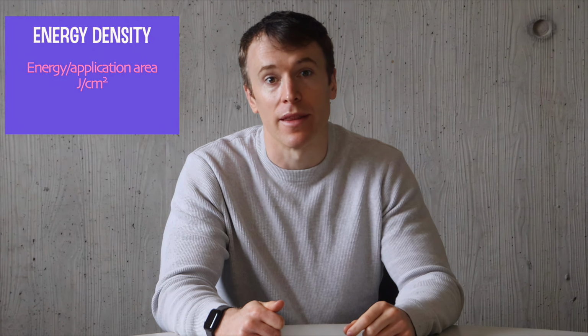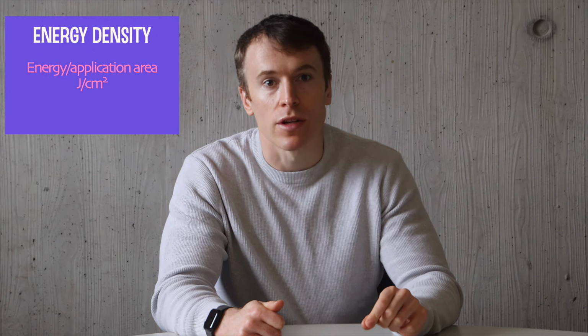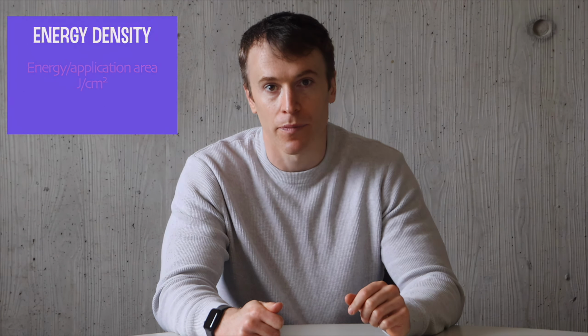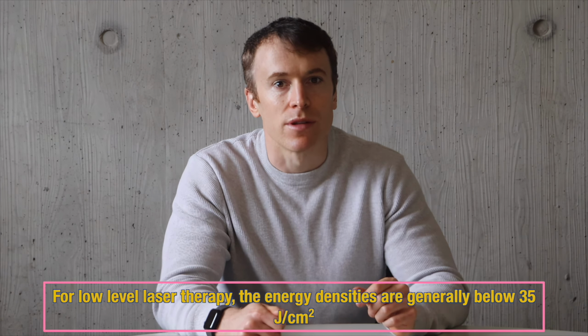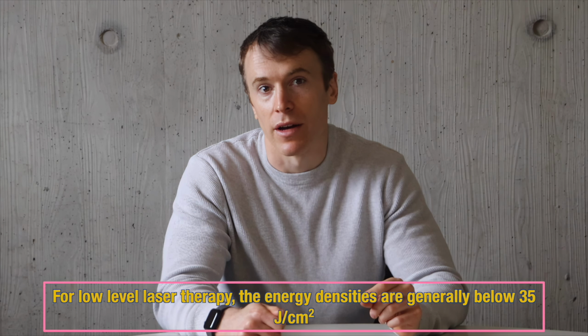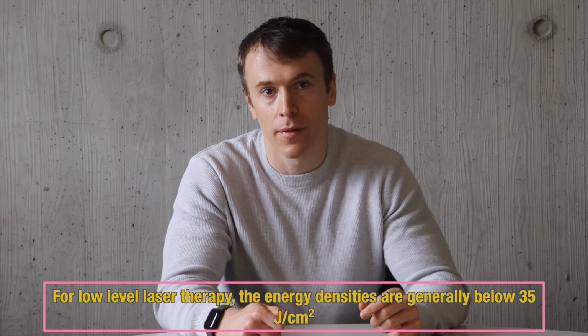Next, the amount of energy that is delivered. Energy is measured in joules, and fluence, or energy density, is energy divided by the application area, so its units are in joules per square centimetre. When it comes to medical lasers, the destruction of large tissues or structures requires high fluence due to the amount of tissue that needs to be heated to achieve thermal coagulation. But for low-level laser therapy, the fluence is generally below 35 joules per square centimetre.